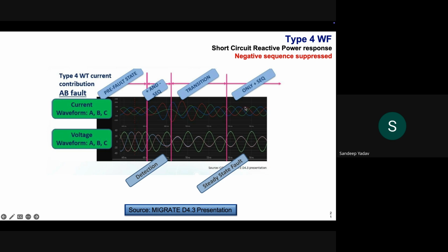So that is why conventional relays, for example the distance relays, have a difficult time detecting the fault, because the magnitude has not changed much. The current has not risen considerably, and at the same time, there is no negative sequence or zero sequence current to determine the directionality of the fault. So we'll have a closer look in the upcoming slides at why.